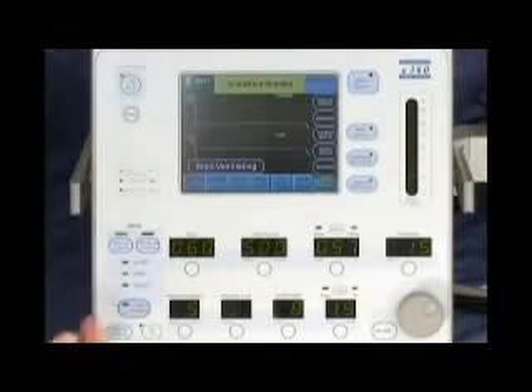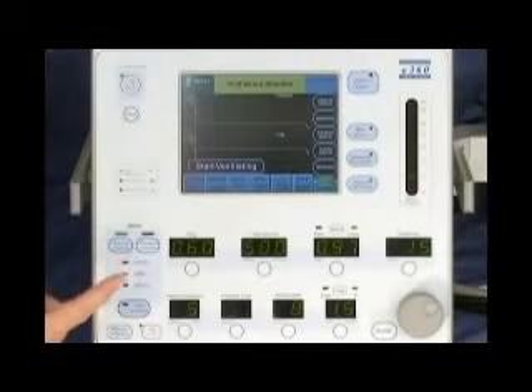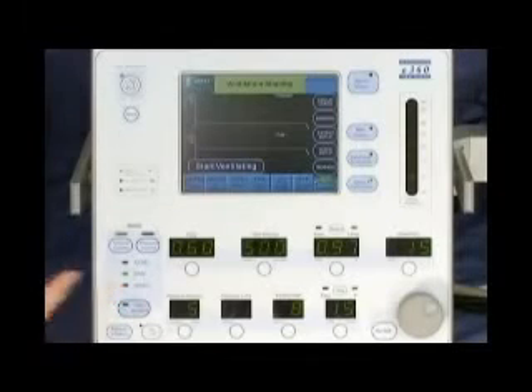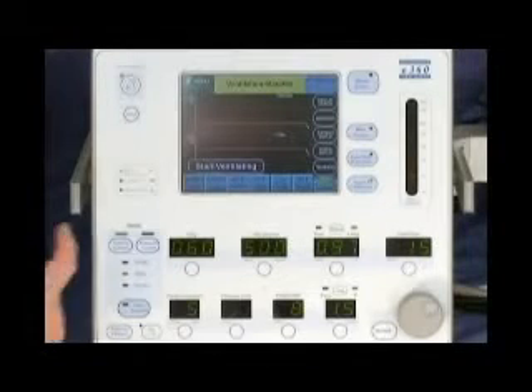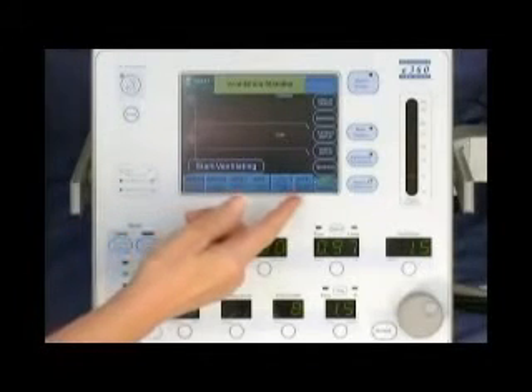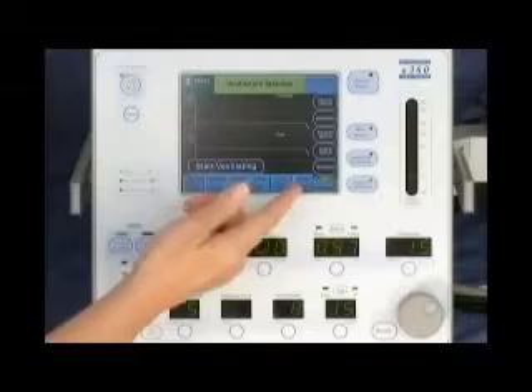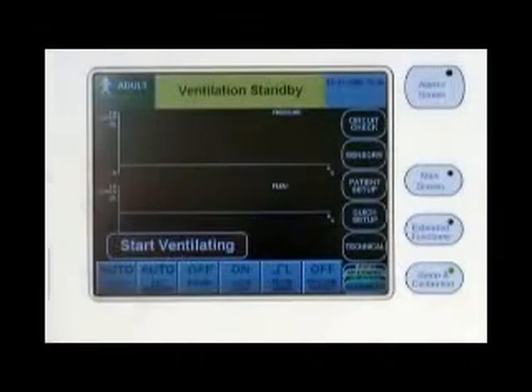On the left side, you'll find the selectors for two of the breath types, volume and pressure control, as well as the indicators for assist control, SIMV, and SPONT modes of ventilation. Controls for activating the other two breath types, biphasic pressure release ventilation and volume target pressure control, are found in the advanced data set on the graphical user interface. The graphical user interface contains the advanced ventilation settings, alarm settings, ventilator setup settings, and monitored data.